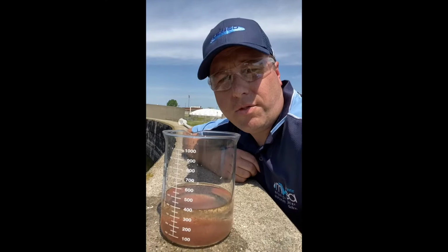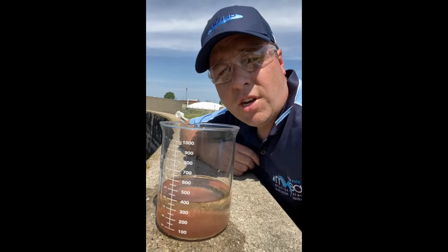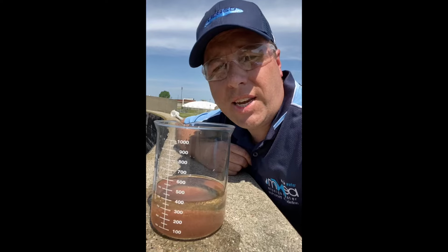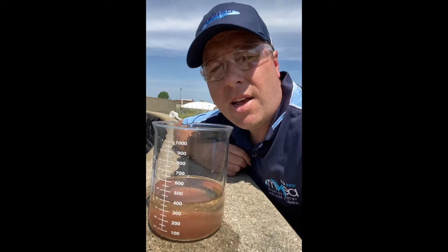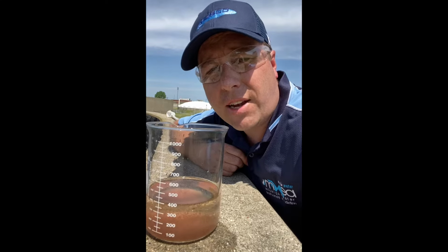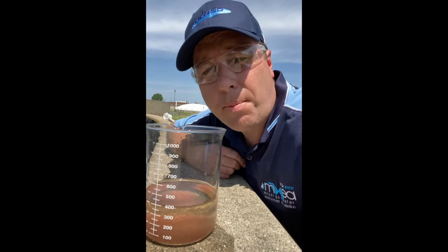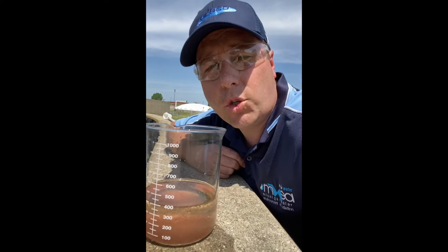So the presence of these water fleas in my oxidation ditch and the clarifier is an indication that it's upset. It's not very healthy. As an incubator, again, I have not kept the conditions right to culture the correct populations of organisms for treating the water.